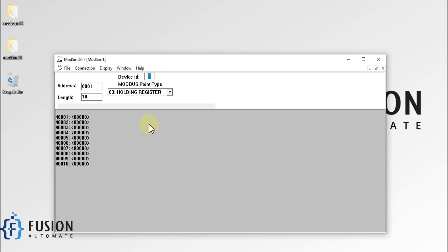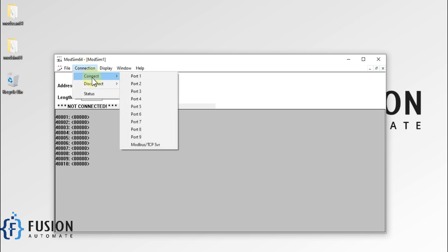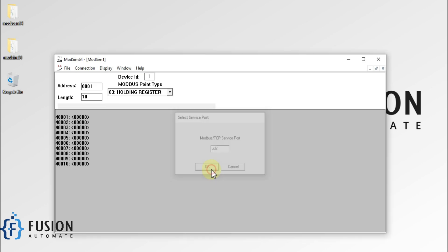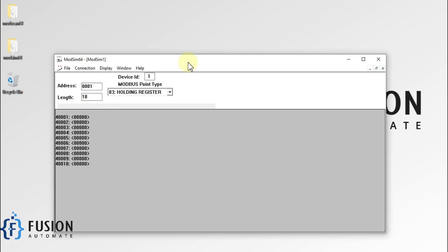Now I want to create this Modbus TCP server, so I have to go to Connection and navigate to Connect. Here you can see Modbus TCP Server — just click on this one. You can see the Modbus TCP Server port is 502. You can change the port here, and then just press OK.